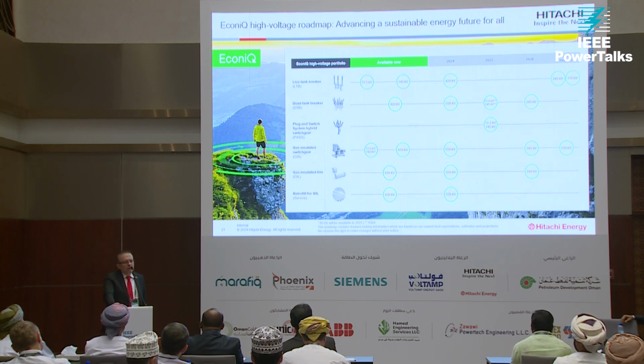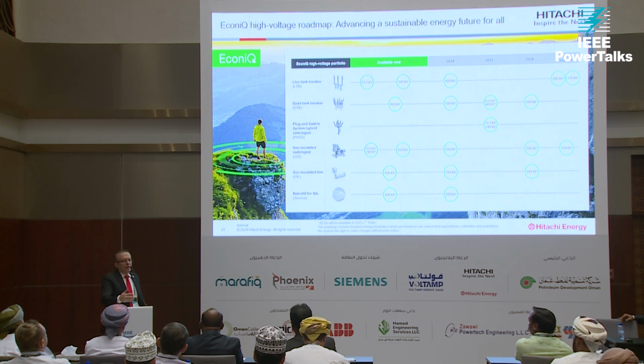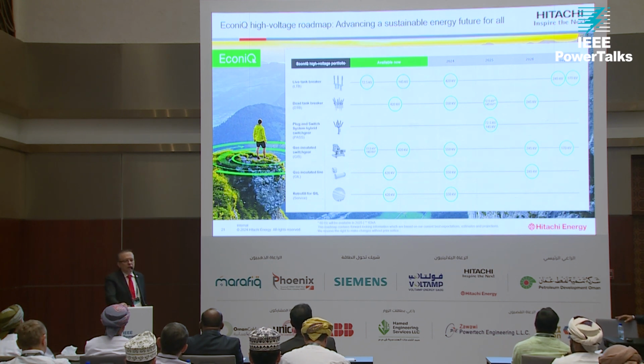But with retrofill, we use the existing GIB and replace the SF6 gas with the EconiQ gas. We'll evacuate the gas inside that GIB, change the flanges and gas gauges, and then fill it with the new EconiQ gas. It's very important, from a life cycle point of view, that we are using the same material.